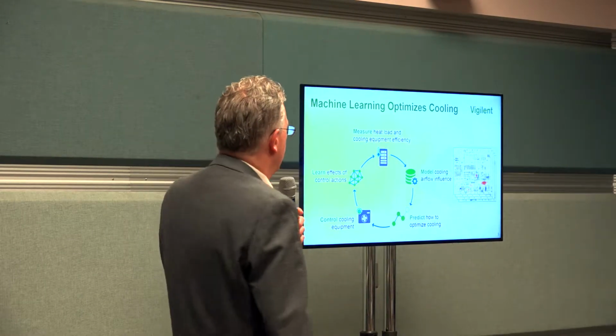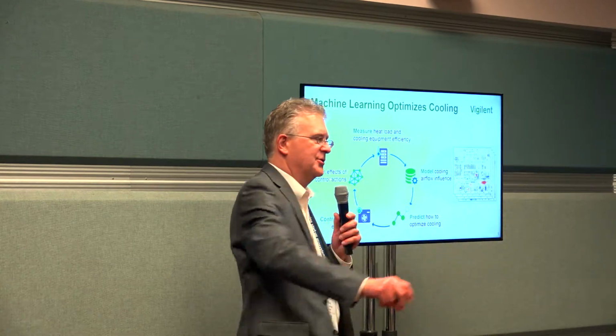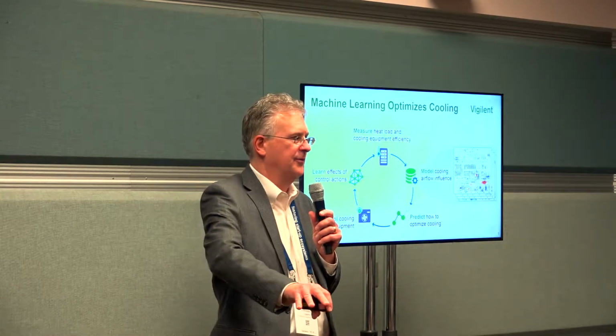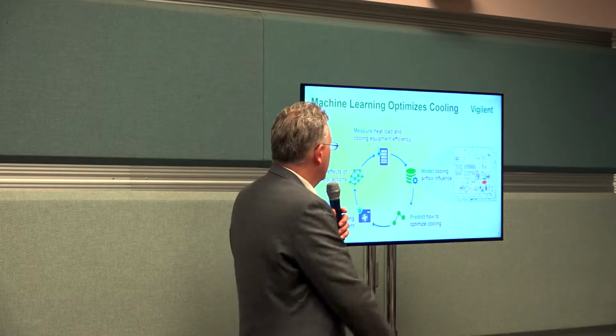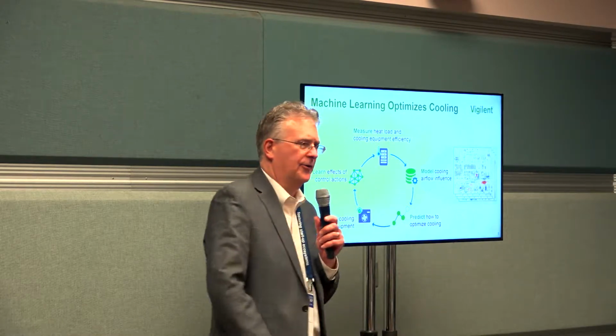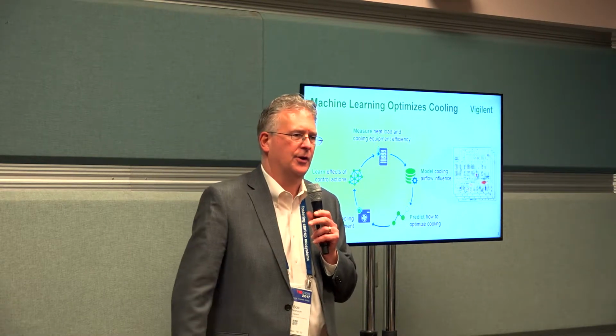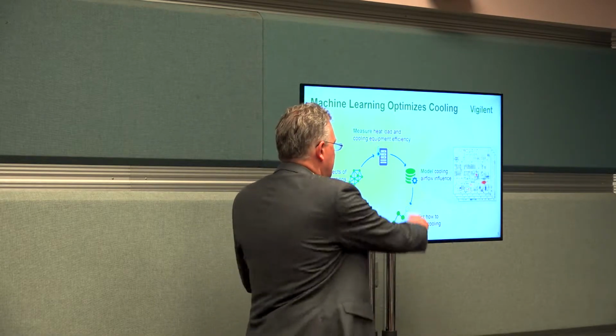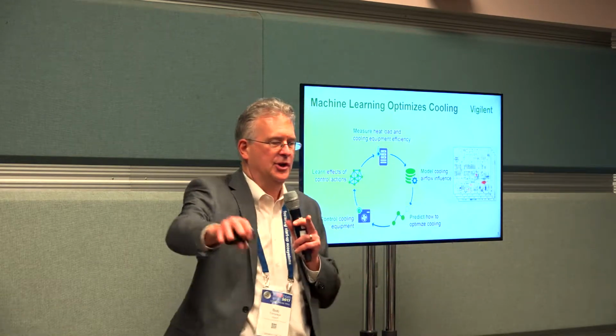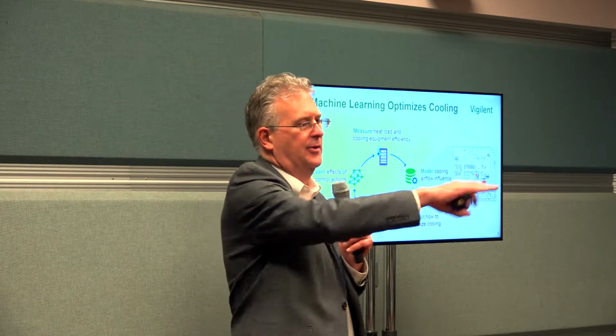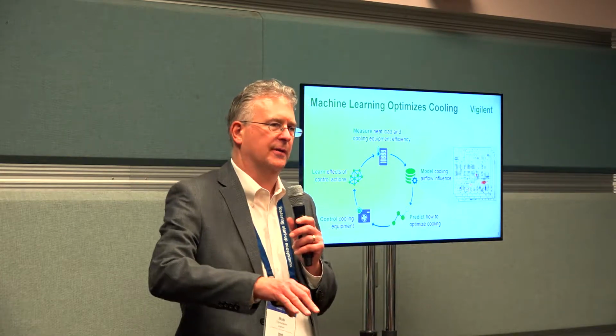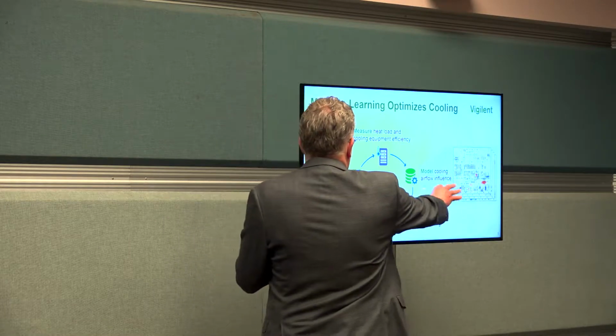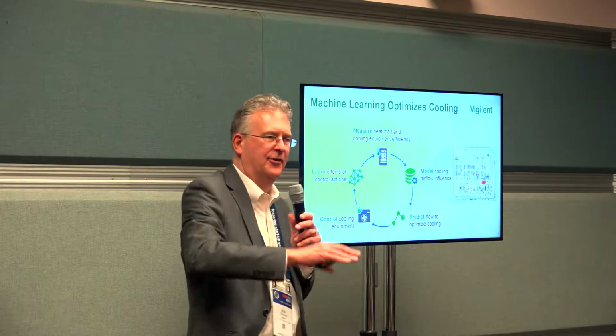The way we use this is we'll put out sensors, if people don't already have them, where the IT equipment is, and wireless equipment to measure the efficiency of the cooling units. Then the machine learning will start to adjust the cooling units and measure the thermal influence across the room, doing this for each air conditioner. It stacks up these influence maps, these influence models, and develops an overall predictive understanding of cooling in the room.